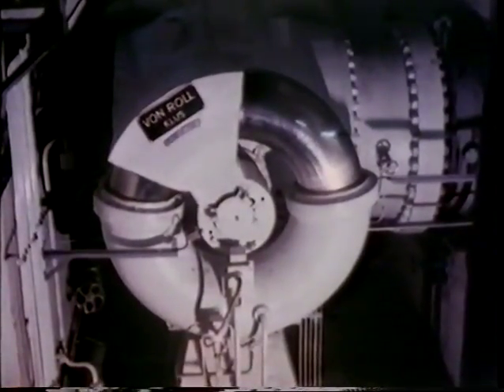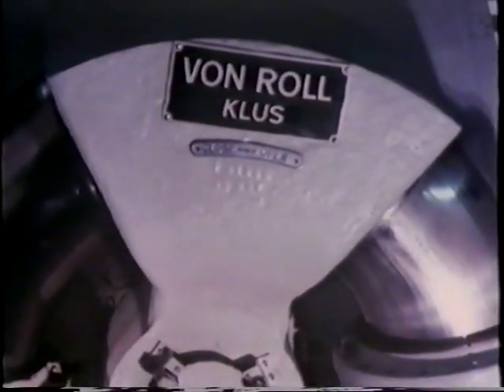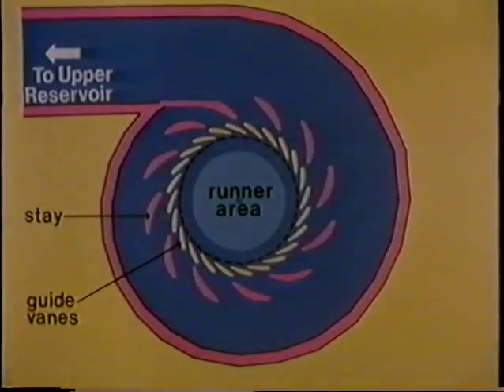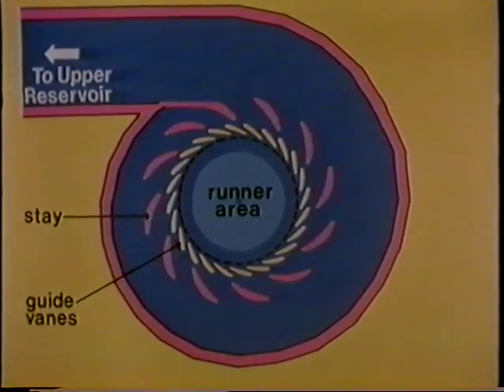The operating servo utilizes the penstock water pressure. It is toroidal in shape, a design which transmits its reactions back into the body of the valve. The water to and from the stay ring, which has 12 stays, is regulated by 24 guide vanes. Stay rings are 1.5% manganese steel cast in two halves which were bolted together and welded on site.